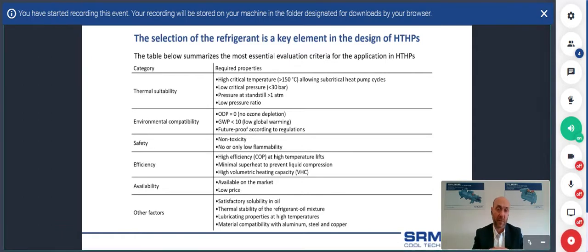compatible with the environment. So the ozone depletion potential, expressed by the ODP value, has to be 0. The refrigerants now used can no longer have ozone depletion potential. The global warming potential should be as low as possible, normally lower than 10. It also has to be non-flammable and not toxic because of the safety of the application. Of course, these are not enough. We also have to evaluate the efficiency of the system with the refrigerant applied, the minimal superheat, the behavior of the refrigerant with the lubricant, availability on the market, and low price. So we have to check several things.